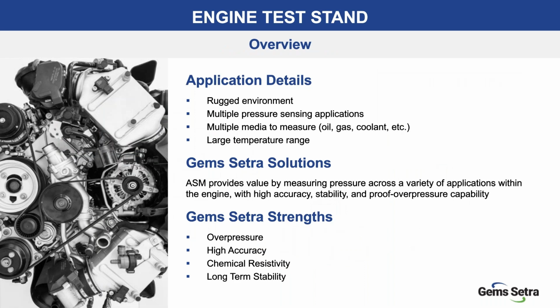Key requirements in the application include the ability to support a rugged environment, which our products meet. As you can see from many of the applications that I reviewed before, it requires multiple sensing application requirements, multiple media for measuring, and a wide, large temperature range. Along with the other products supporting the engine test stand application, the ASM provides value by measuring pressure across a variety of those applications at high accuracy, stability, and with that proof pressure capability. Our strengths in this application are overpressure capability, high accuracy, chemical resistivity, and long-term stability.